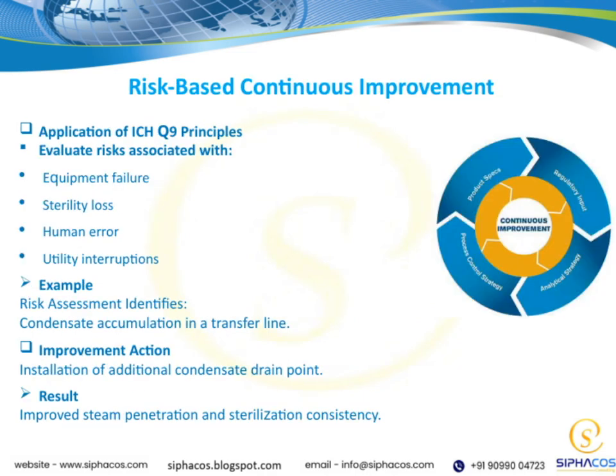Let's talk about risk-based continuous improvement using the principles from ICH Q9. We start by evaluating risks, things like equipment failure, sterility loss, human error, and utility interruptions. For example, a risk assessment might reveal condensate building up in a transfer line. The improvement? Adding an extra condensate drain point. This simple change leads to better steam penetration and more consistent sterilization. It's a clear case of identifying risk, taking action, and improving quality.